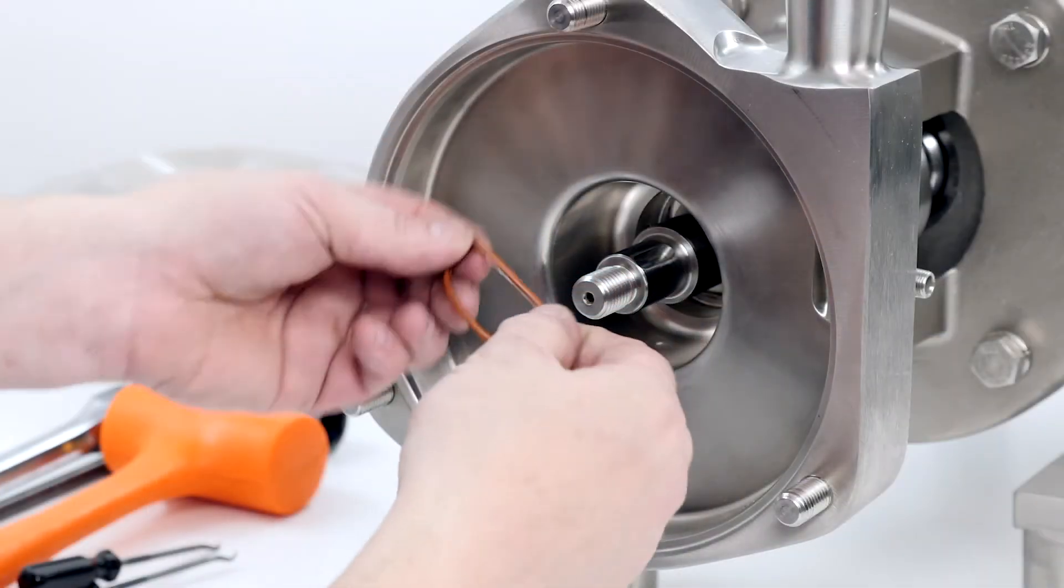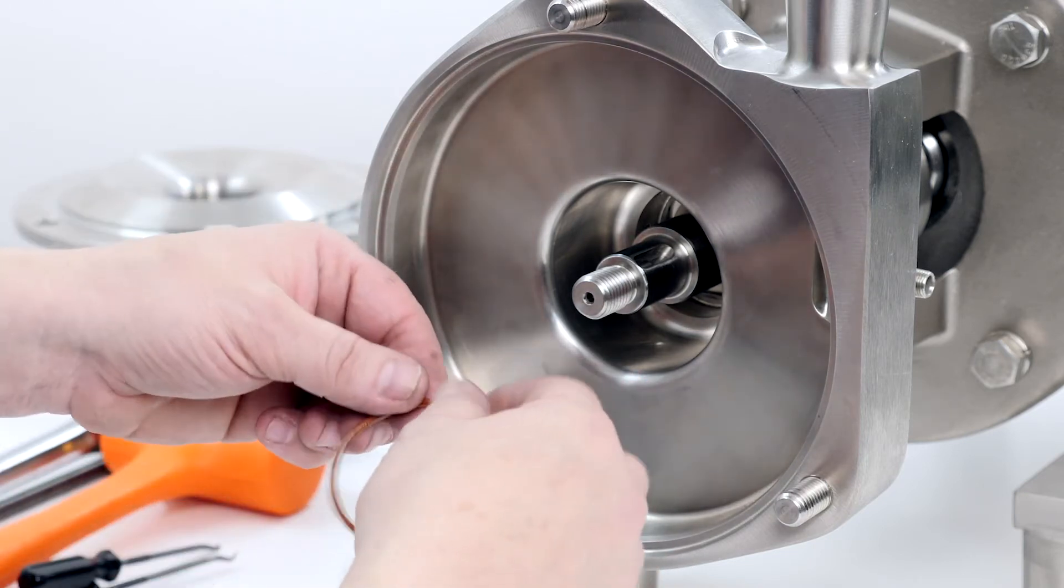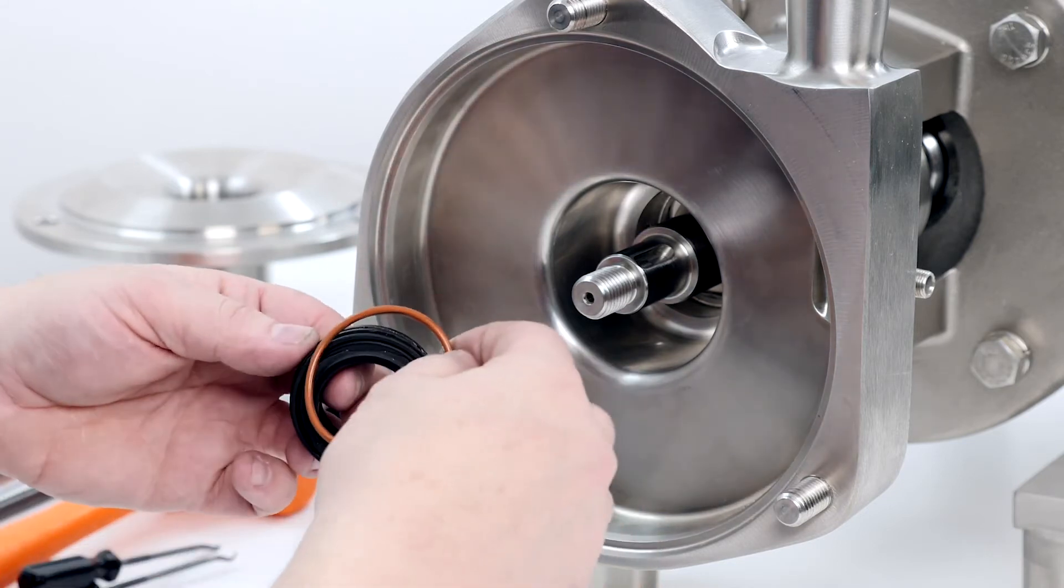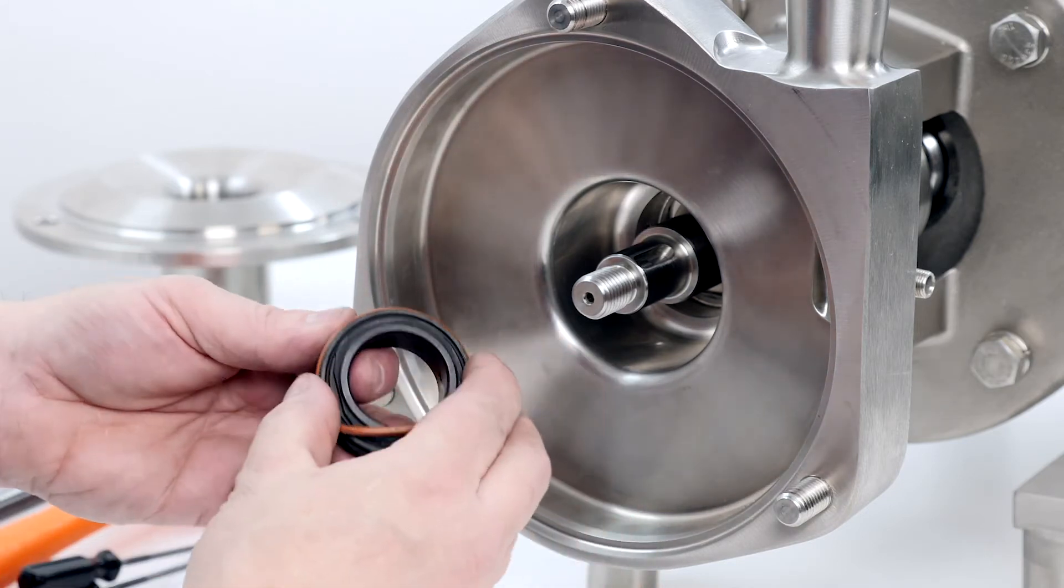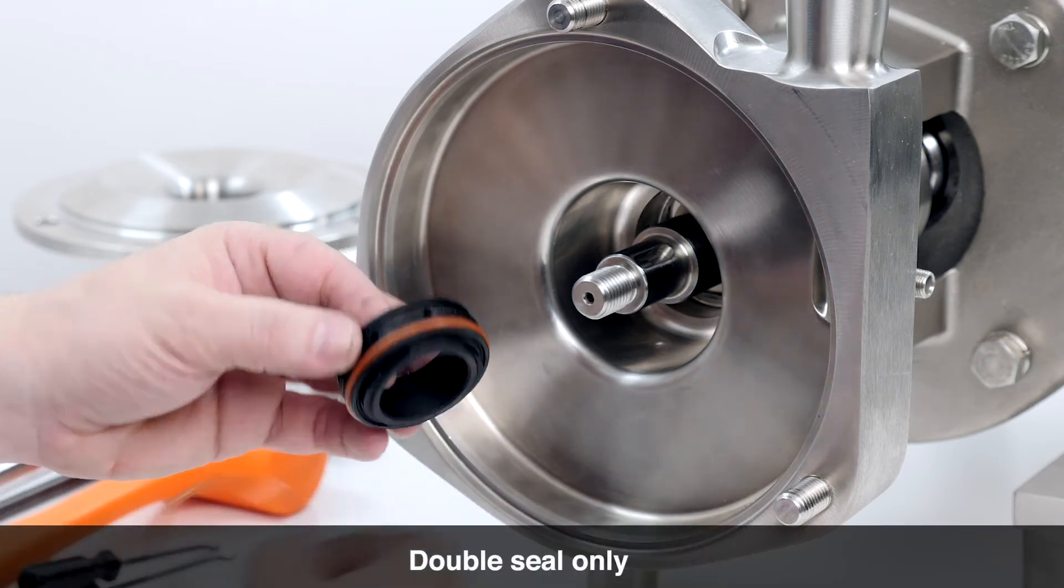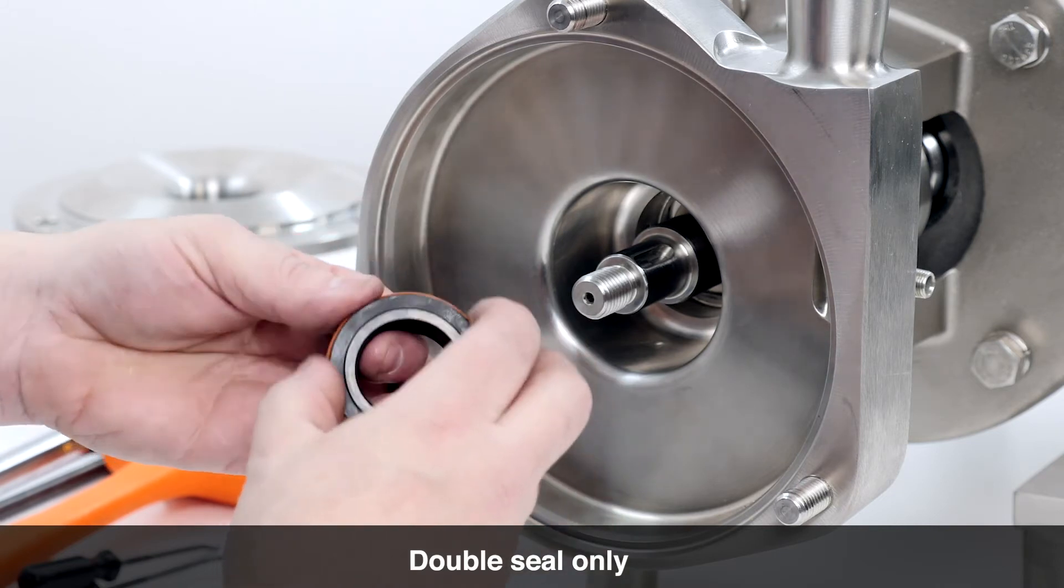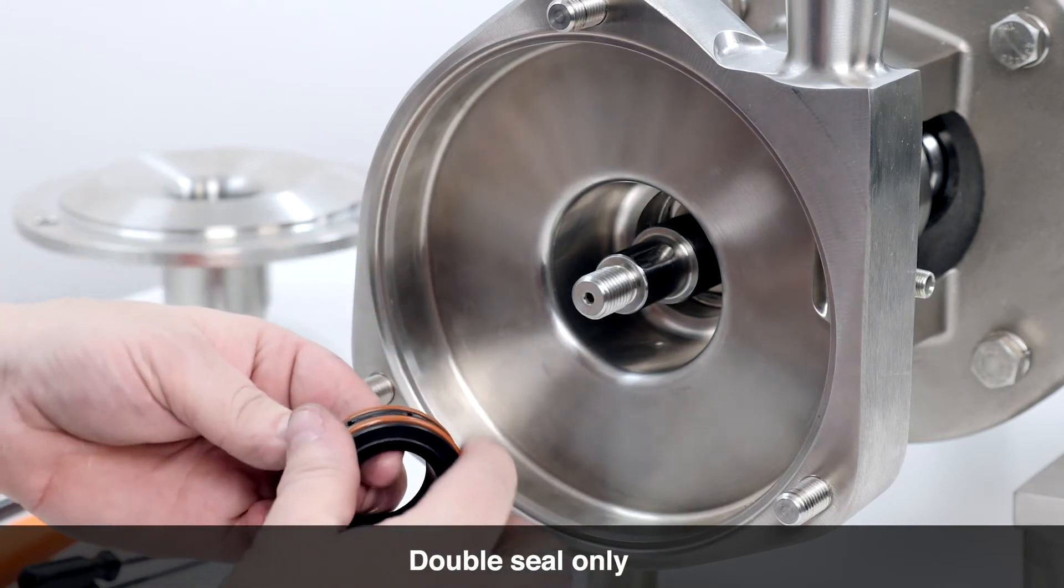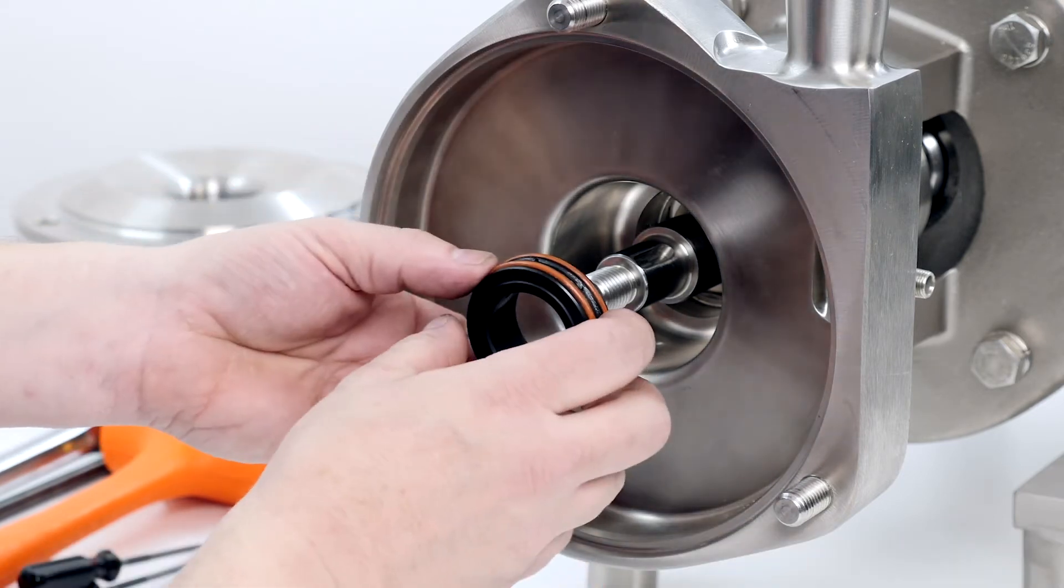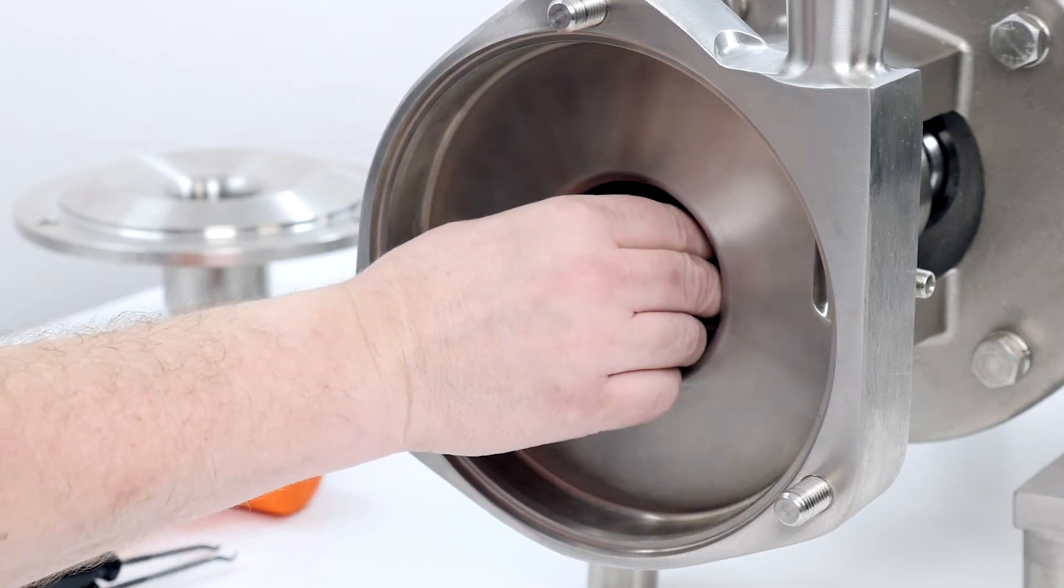Lubricate and install the stationary seal O-ring onto the stationary seal. Double seal only: Install a second O-ring into the additional groove. Install the stationary seal into the housing, making sure to align flats on the seal with the flats on the housing.